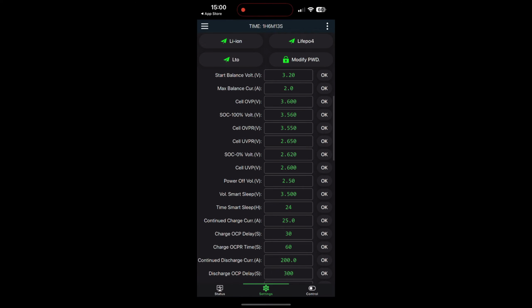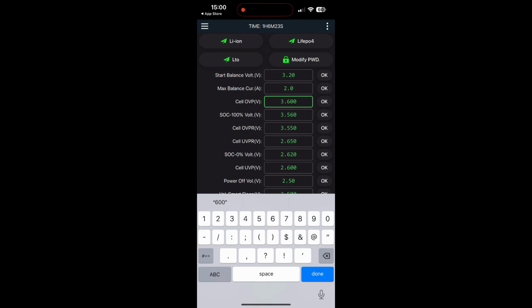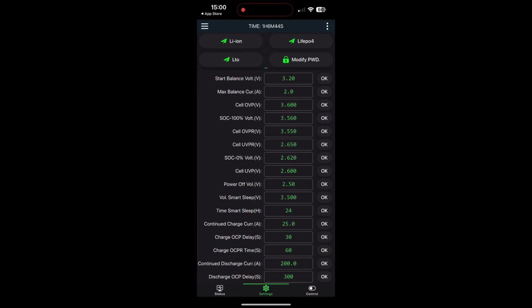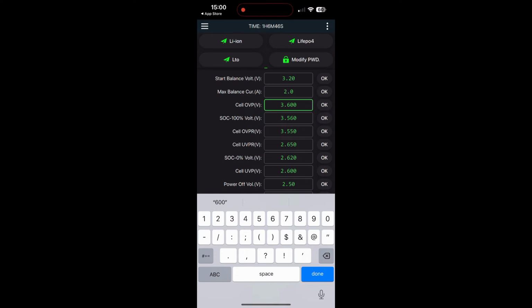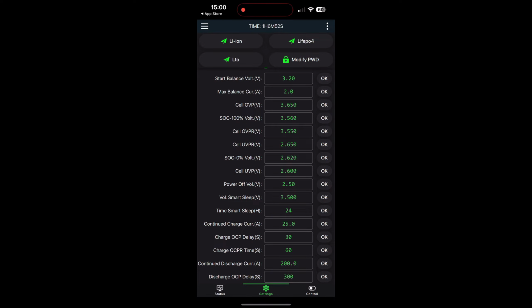Okay. Now, cell OVP, which stands for over voltage protect. What that basically means is what's the highest that you want the voltage to be. Now, we used to set this to 3.6. Okay, the reason being is that it gave us a little bit of a buffer between the very highest voltage of these cells, which is 3.65, and where the BMS would turn off. Now, because the settings in this BMS have been updated since last doing our video, I'm now happy to set this at 3.65, and I'll tell you why in a second.